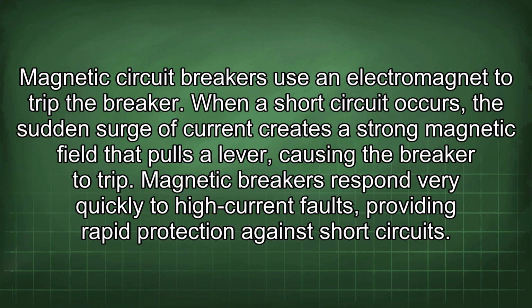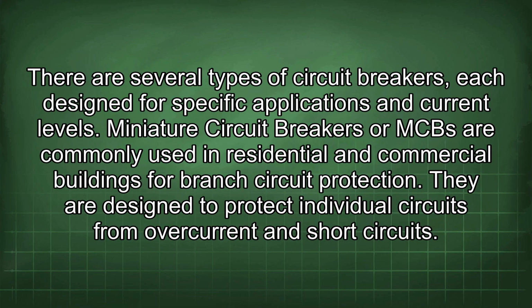Magnetic circuit breakers use an electromagnet to trip the breaker. When a short circuit occurs, the sudden surge of current creates a strong magnetic field that pulls a lever, causing the breaker to trip. Magnetic breakers respond very quickly to high current faults, providing rapid protection against short circuits. There are several types of circuit breakers, each designed for specific applications and current levels.